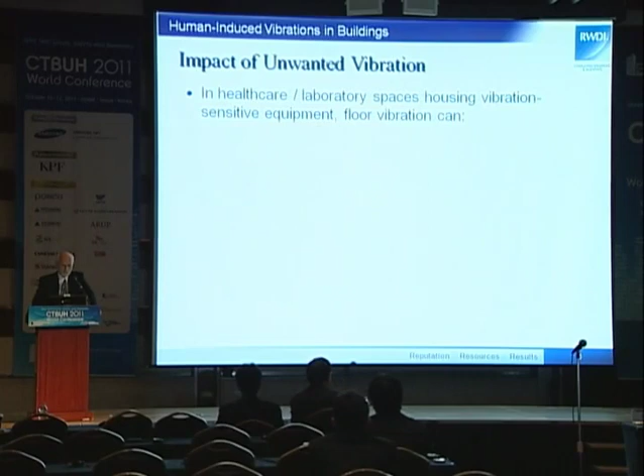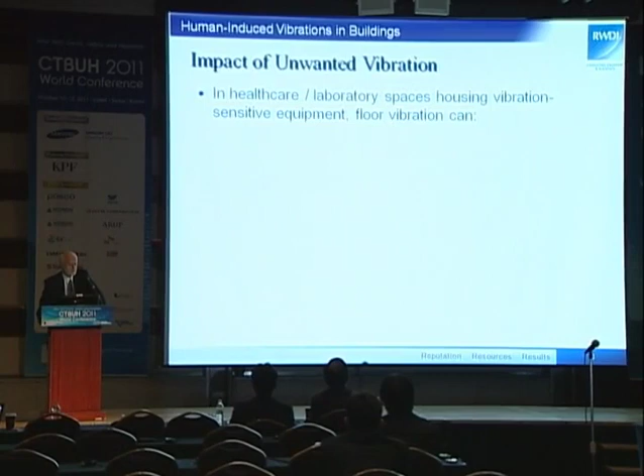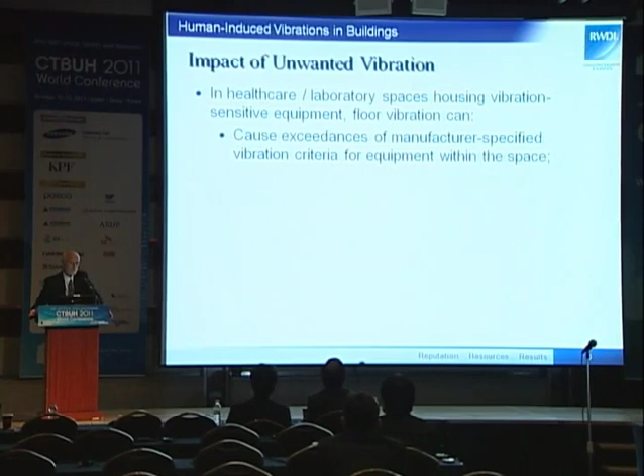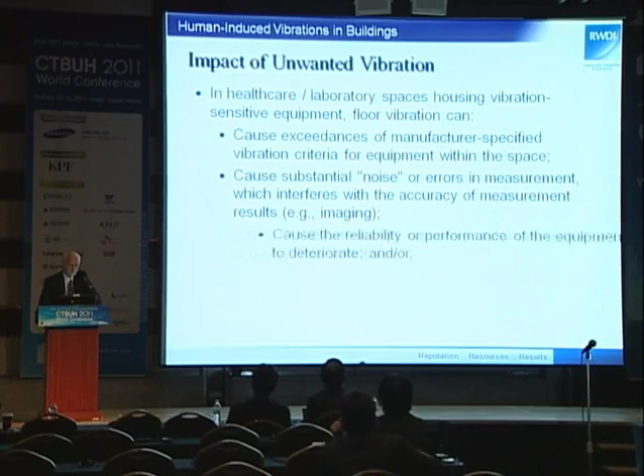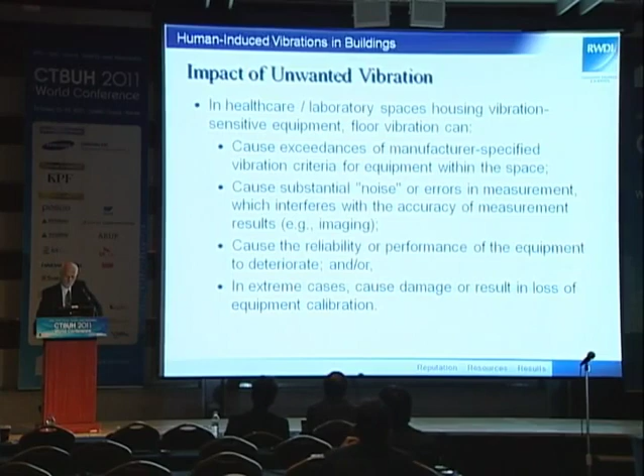And in healthcare and laboratory spaces housing vibration-sensitive equipment, the floor vibration can cause exceedances of the manufacturer's specified limits. The reason they have these limits is, of course, you get substantial noise or errors in the measurement or in the image that you get out of the equipment if you have excessive vibration. And in the end, the reliability or performance of the equipment can deteriorate over time due to continuous vibration, and it can even throw off the calibration. This can obviously be quite expensive to fix.